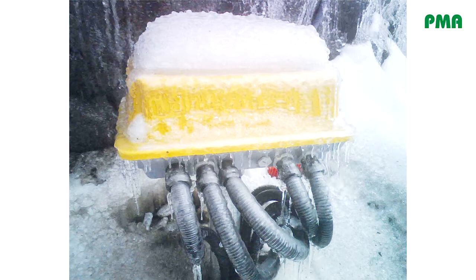Yes, that's a typical European Alps situation, but it can also be out in the Rocky Mountains, where you see what's happening to these kind of boxes. In winter time they look like this. You even see the water in form of ice trickling down. So we have to make sure ingress protection is definitely as needed, IP66, maybe IP69, when cleaning with water stream. So this is one thing.